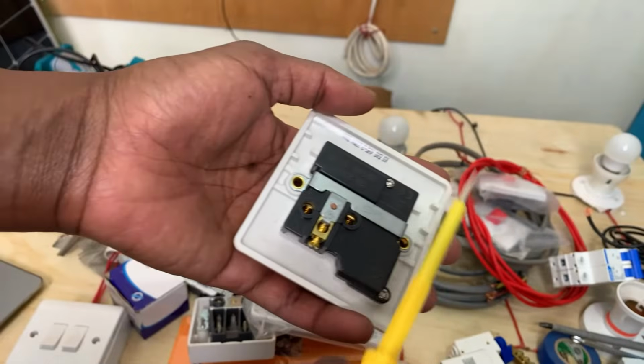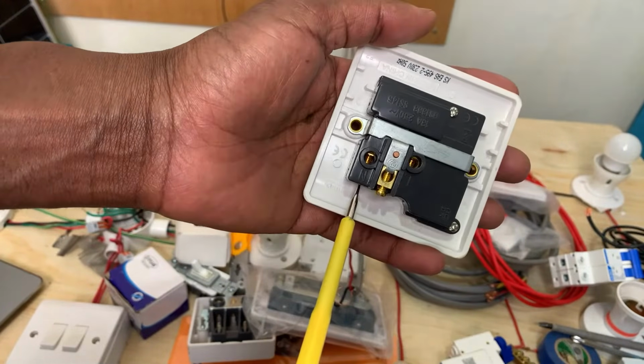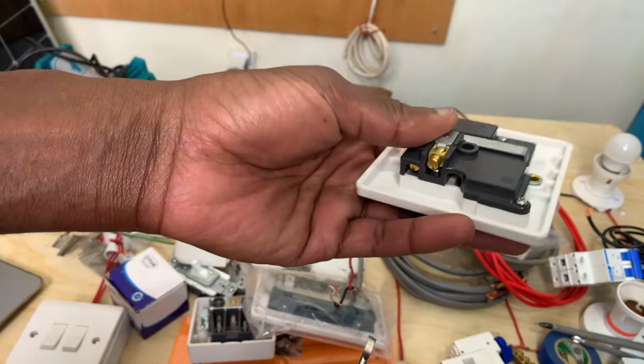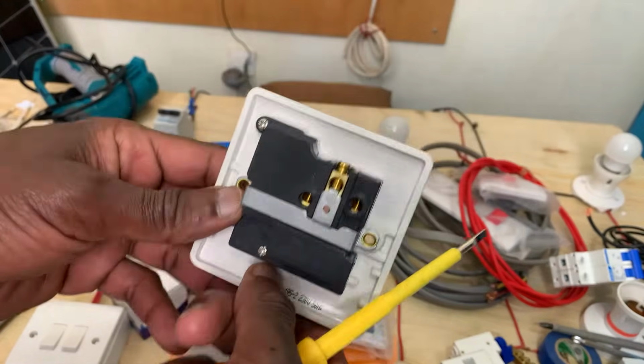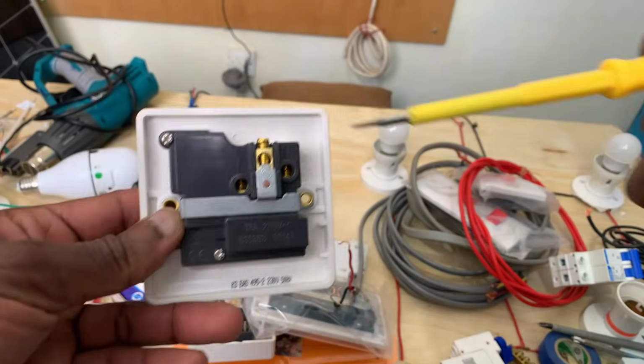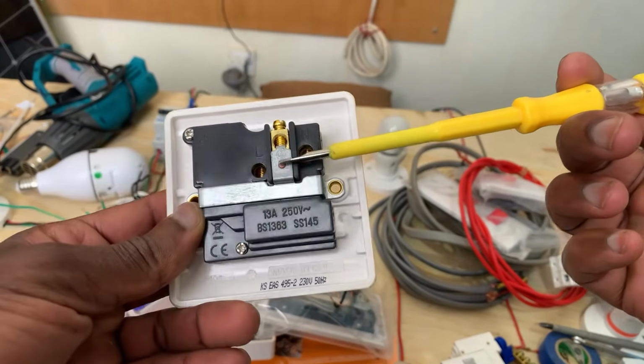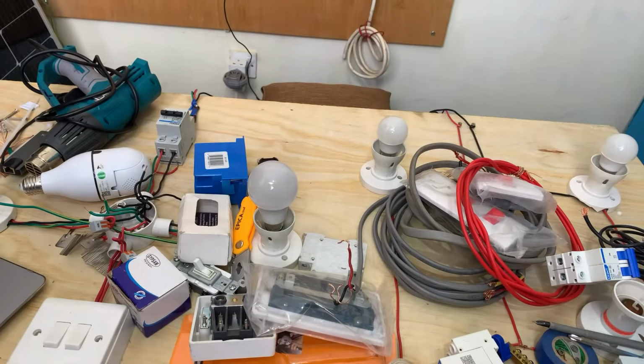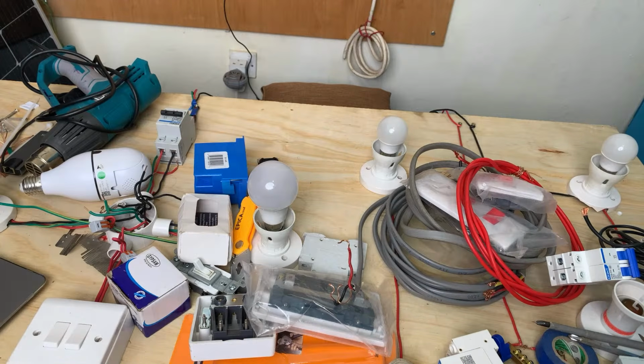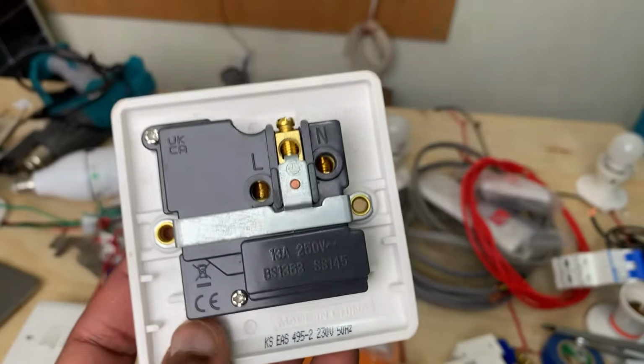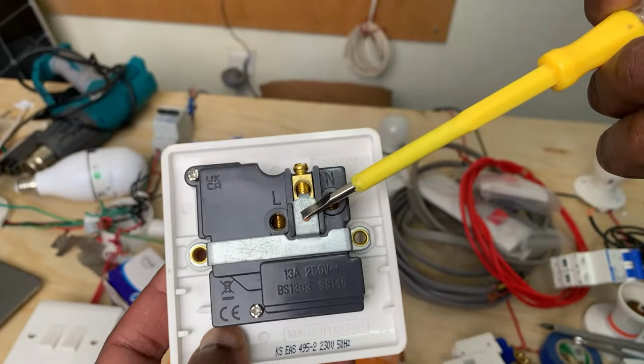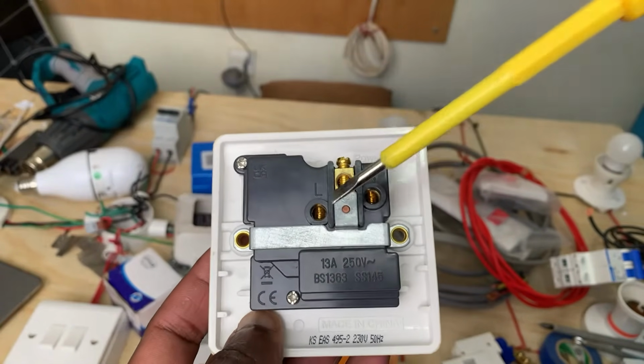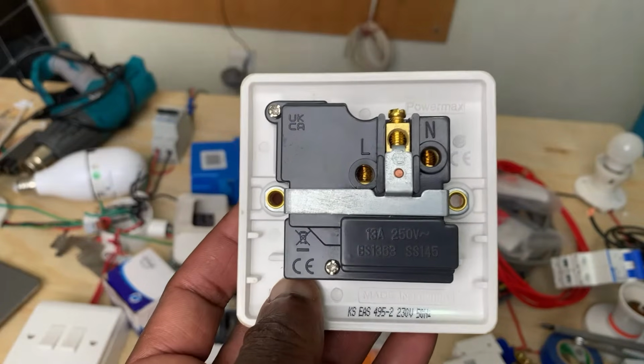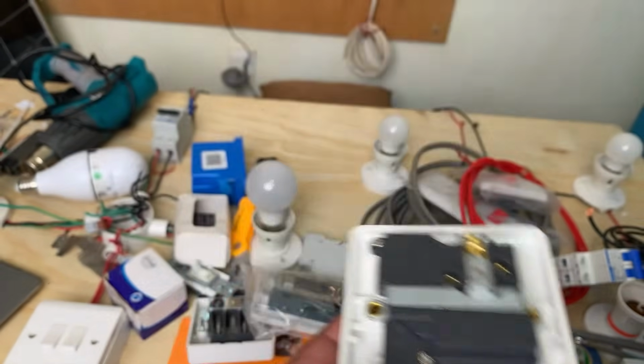A phase tester is only to test for the presence of current flowing either in the phase or the neutral. We're not saying we shouldn't test the earth with a tester too. It's important because sometimes there's a huge problem, leakage, and the protective devices are not working, poorly connected, or malfunctioned. So even the neutral and the earth connection may have current flowing through it. We want to make sure we use a tester for that purpose.